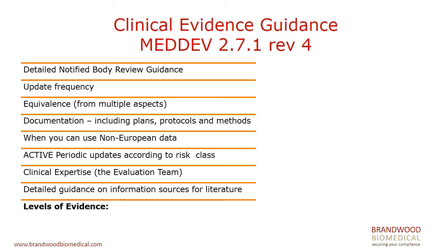The concept of equivalence, really borrowing from the 510K paradigm in the United States, considering equivalence with predicate devices, is now embedded in the clinical evidence guidance. That equivalence needs to be looked at from multiple aspects, not just direct clinical performance data, but whether the device is equivalent to other established safe devices in terms of things like mechanical and biological safety. So from your preclinical data, is your device equivalent to other established safe devices in the market?